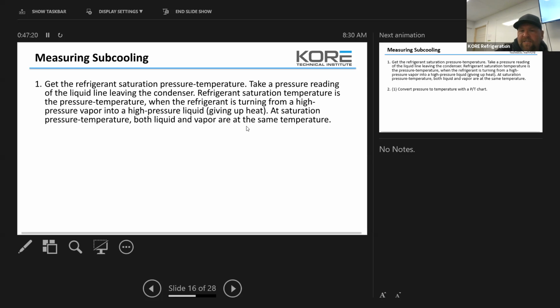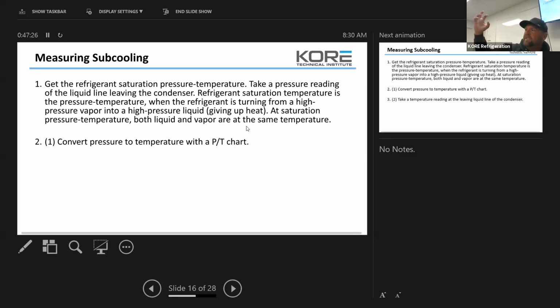That's wrong. They're at the same pressure. Okay. Not temperature. So when you're condensing, there will be a temperature change, but your pressures won't change much. So when you're at the condenser, whether you're at inlet or outlet, your pressure's not going to change much. Your temperature will change. The sensible heat will change. So you'll be able to feel that conversion from gas to liquid.